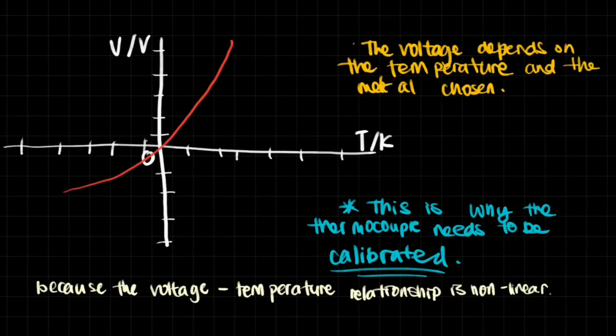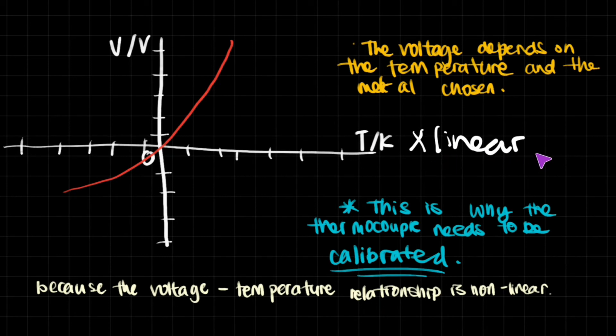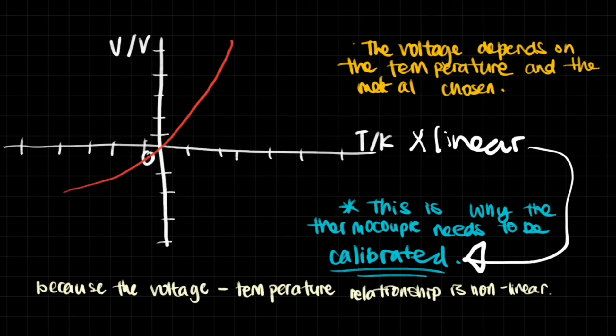To extrapolate on thermocouples: the voltage depends on the temperature and the metal chosen, which is why these thermometers need to be calibrated. If you plot temperature versus voltage, you see that it is not a straight line — it's not linear. At lower temperatures, there tend to be lower changes in voltage, and then at higher temperatures, it suddenly becomes very large changes in voltage. This graph is helpful to memorize because the voltage-temperature relationship is nonlinear. The bigger the temperature, the bigger the voltage induced for the thermocouple.